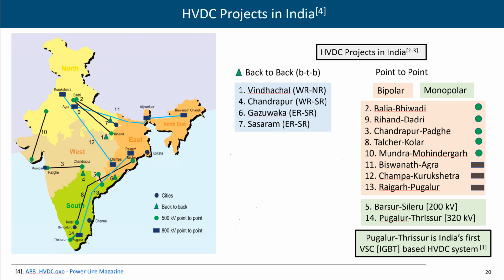So in monopolar, is it positive only or negative? Generally we take negative, because if we take negative then corona discharge is less. That is why we go for negative—interference is also less, that is why negative polarity is preferred. But in bipolar both positive and negative polarity are there, and if there is a fault in one line, negative or positive, we can still supply half the power, with ground used as a return path. So bipolar is more reliable. But initially when we started with monopolar, it was easy to implement.